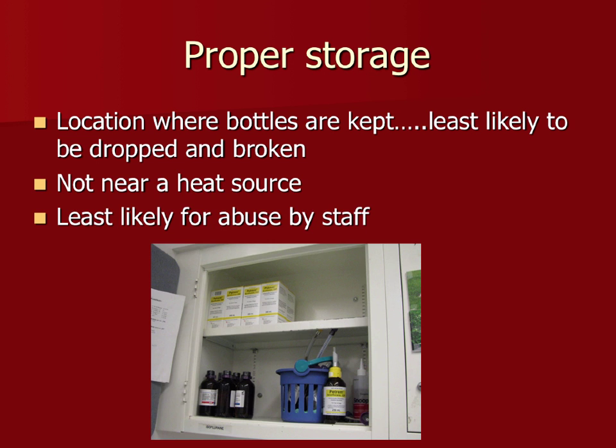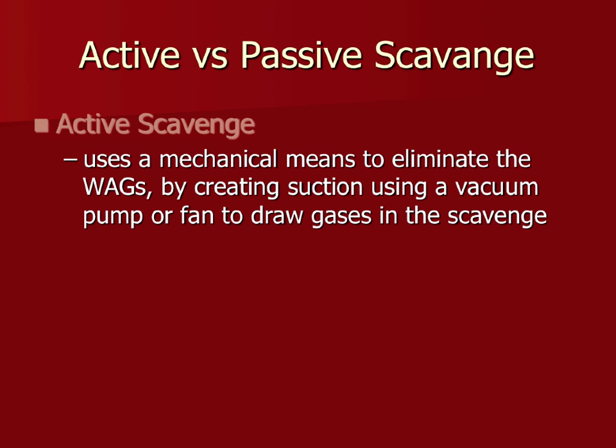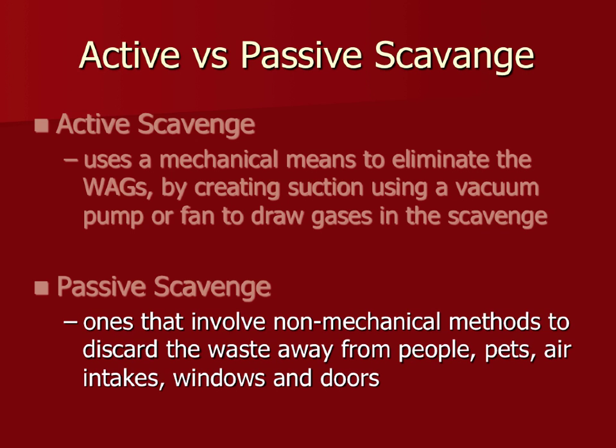Active scavenging uses a mechanical means — suctions and vacuums — to literally pull waste anesthetics out of your machine and into a different environment. Passive scavenging has no active mechanism; it relies on airflow itself moving down a long tube, either out a separate port in the building, out a window, or into a F/air canister.